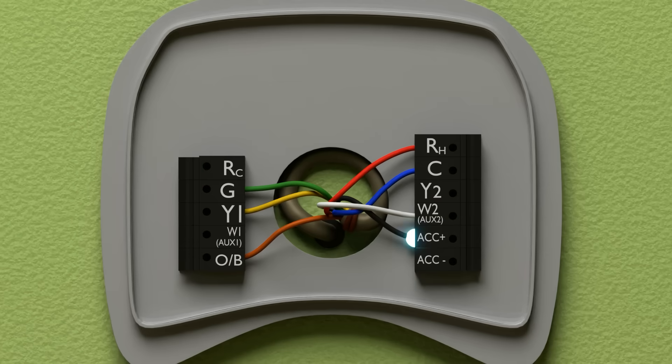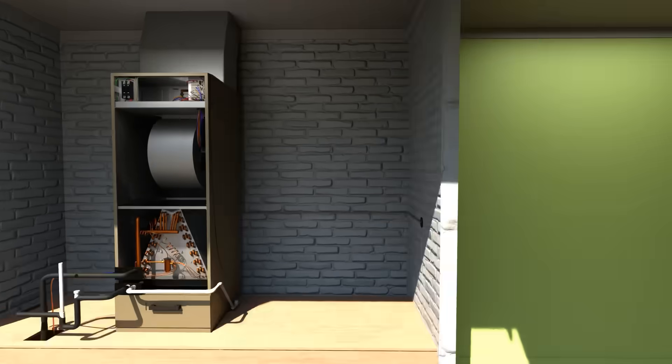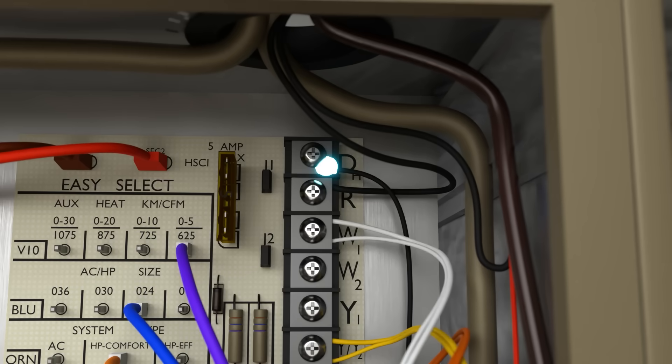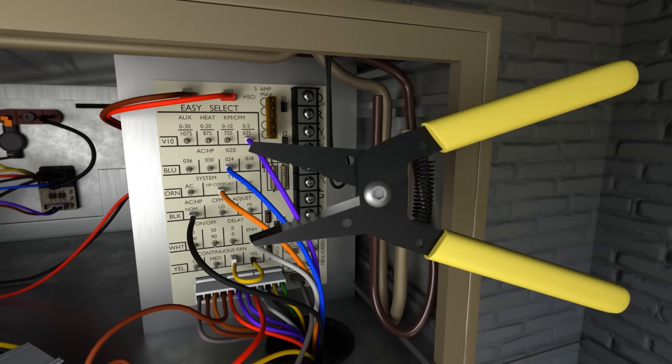In this case, we're using ACC plus to energize the dehumidification terminal on the terminal block. The blower will only come to full speed when the DH terminal is energized by the thermostat.